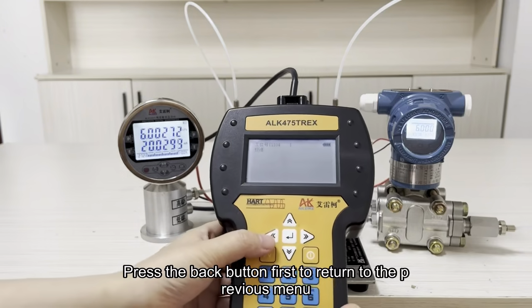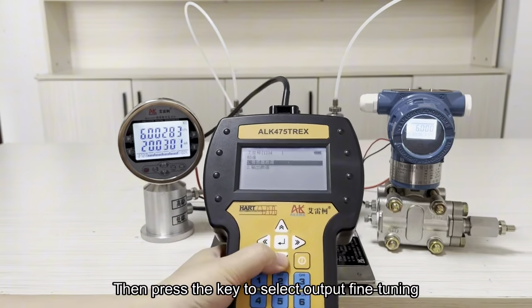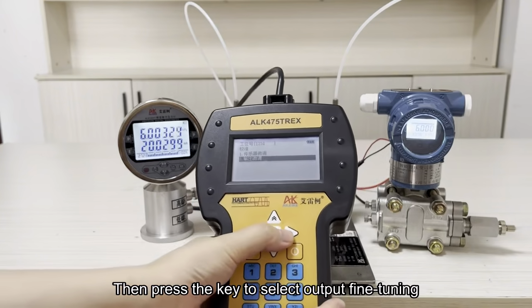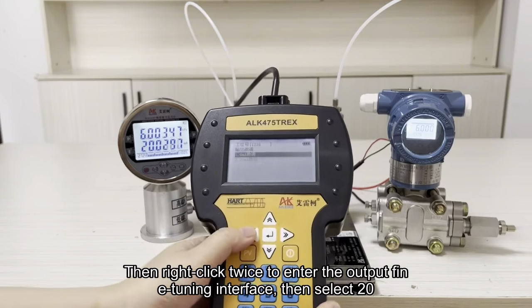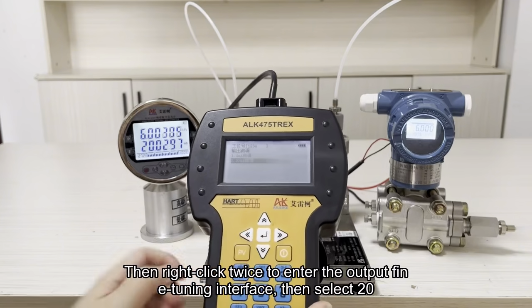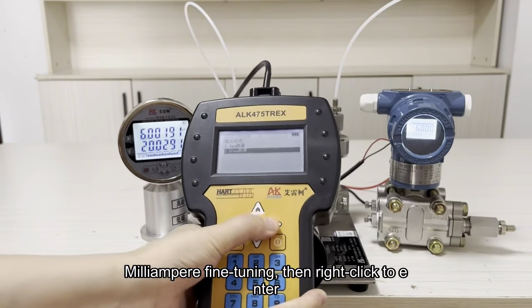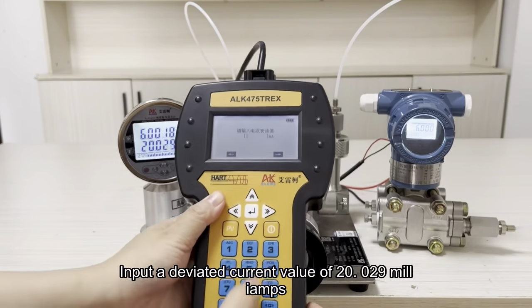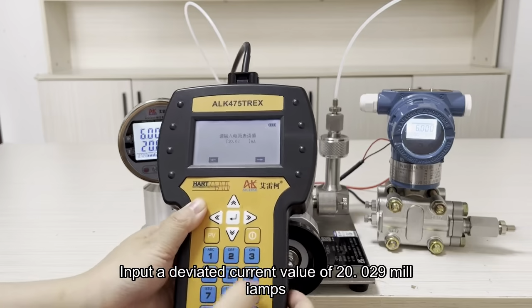Press the back button first to return to the previous menu. Then press the key to select output fine-tuning. Then right-click twice to enter the output fine-tuning interface. Then select 20 mA fine-tuning. Then right-click to enter. Input a deviated current value of 20.029 mA.